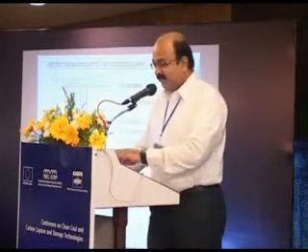Basically, the spaces are there. In the vertical portion that is available, you can always create one more loop, either for the superheater or reheater, and support it from there. You are increasing the number of coils. Yes. That means you have to change the entire header? No. I am cutting off somewhere, creating an extra loop, and then joining it to the original line. So we add a loop there. Now, how much of it is effective is another question, because the gas is taking a turn. But we do factor that in when we do the design and add the surface.